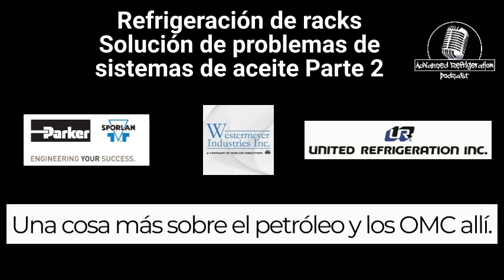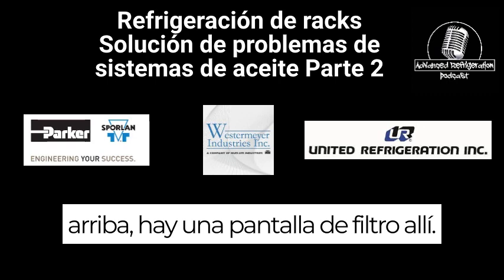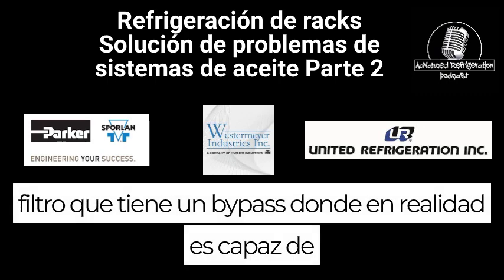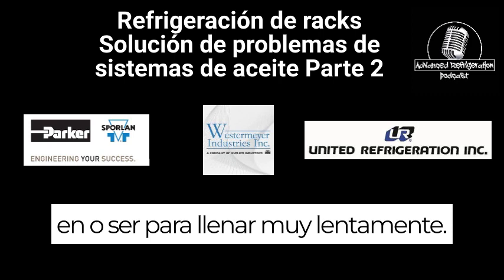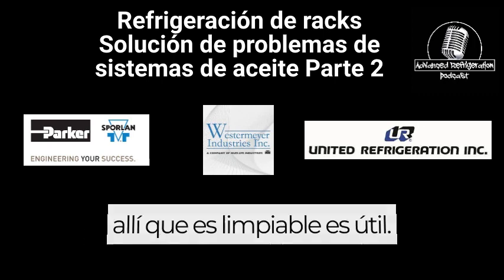One more thing about the OMBs and the OMCs: where the quarter inch oil line hooks up, there is a filter screen in there. So be mindful if you have an oil filter that has a bypass, you could potentially throw garbage into that screen, which could cause your oil not to go in, or to fill very, very slowly. So just be cautious of that. There is also a screen in there that is cleanable and serviceable.